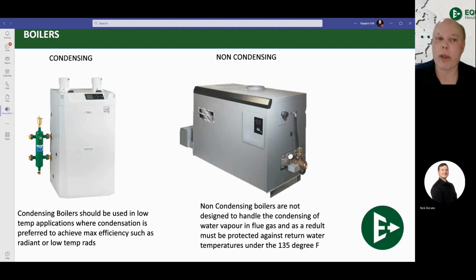So that leads us now into what your standard boilers are. Your standard boilers are going to be a condensing type and a non-condensing type. Condensing type you're going to find primarily in residential homes. That's going to be the vast majority of your boilers. Essentially, what you need to know about a condensing boiler is that you want it to sweat. You want it to condense.